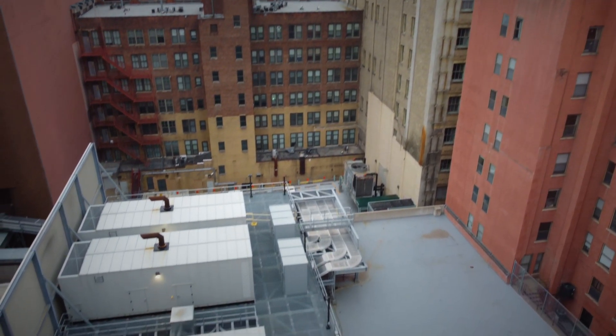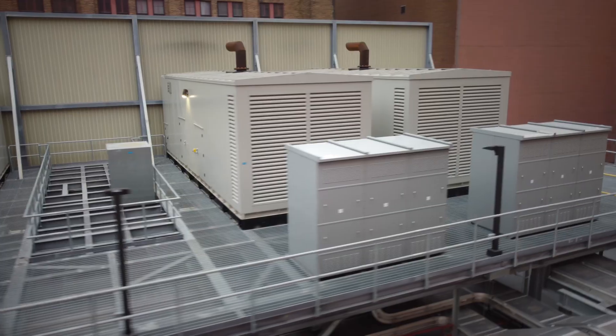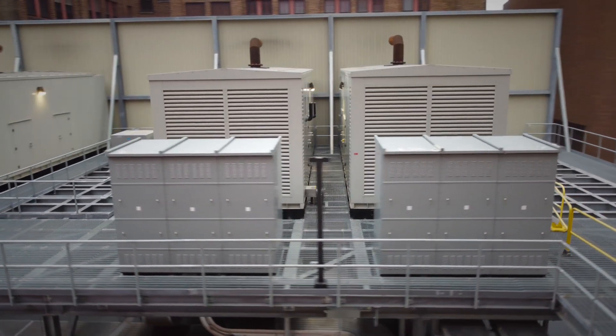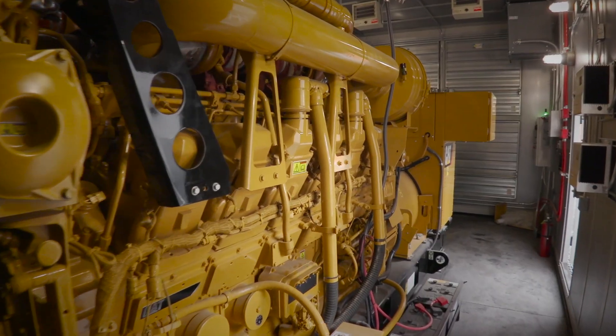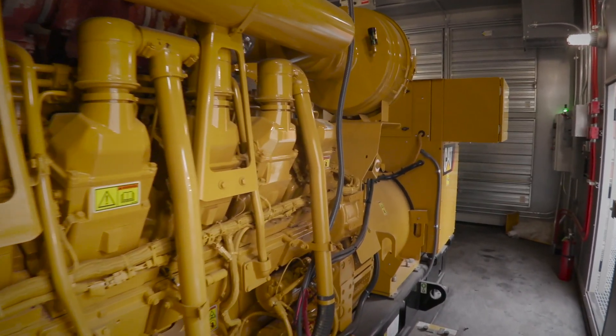In our case, we're in a downtown environment, so having generators that were very quiet was super important — not just for city code, but they also needed to be quiet because we have residential condos and apartments right next to the structure where our generators sit. One thing I was worried about was making that code because at night it had to be 65 dB or less at the property line. Nobody could show me we were even close to being higher than we should be. So we're a good neighbor.